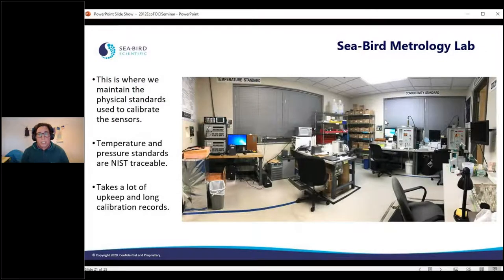This is what our metrology lab looks like. It's not very big, but this is where we maintain the physical standards used to calibrate the sensors. All these temperature and pressure standards are NIST traceable. It takes a lot of upkeep and a lot of long calibration records to do this.